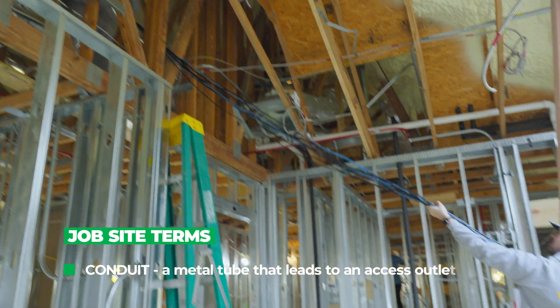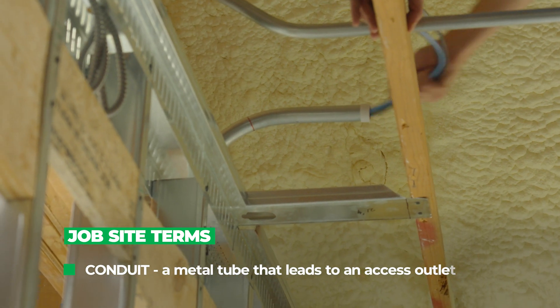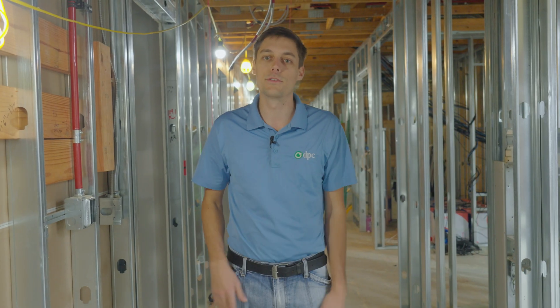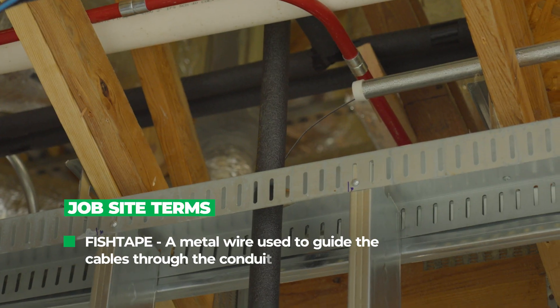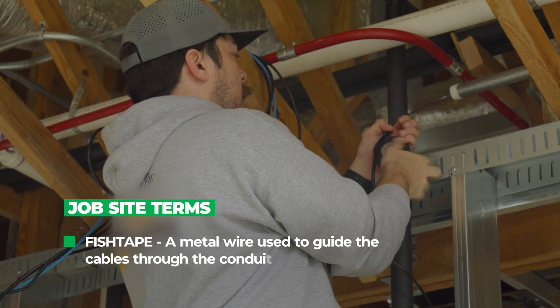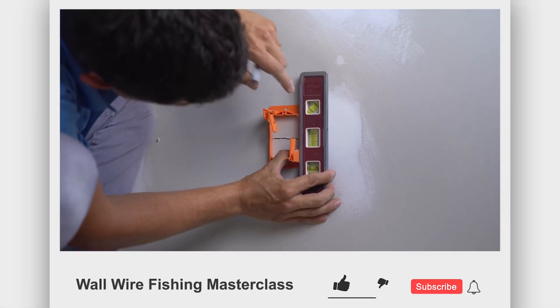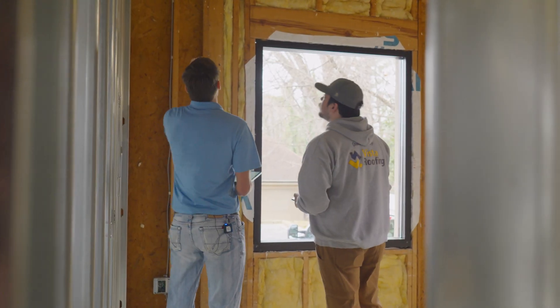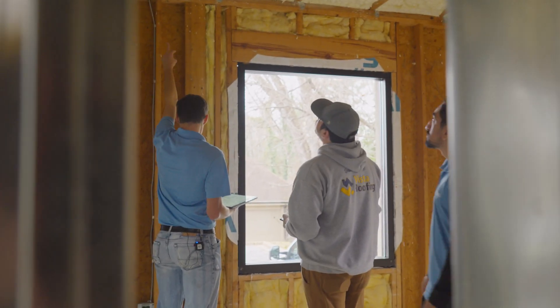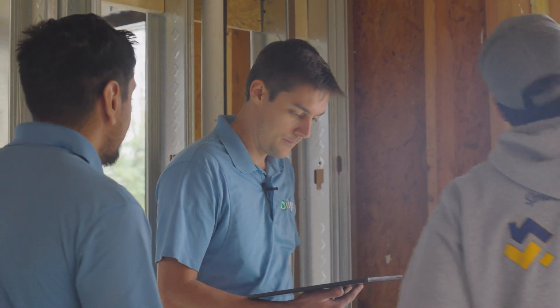As we get into every single room, we have to run down the conduit that's been run for us. We'll either fish the wires straight down the pipe by pushing them, or if it's too constricted or there are too many bends, we'll run a fish tape — a little spool of wire that stays firm so you can fish it all the way up to the top, tape to it, and then pull the wire down. We do have a video about cabling behind walls and how to fish wire — I'll put that in the description below.